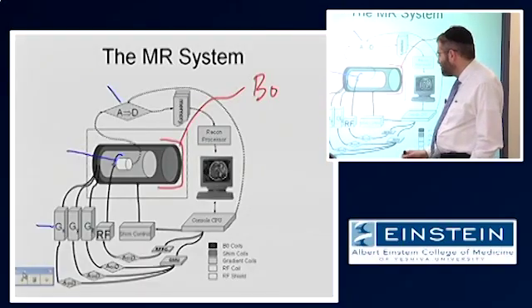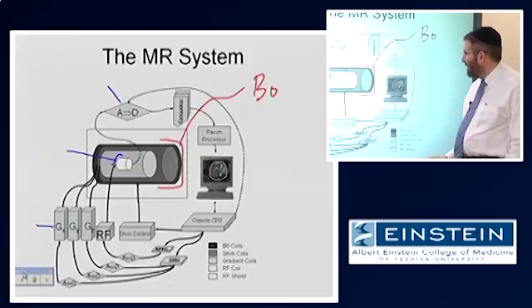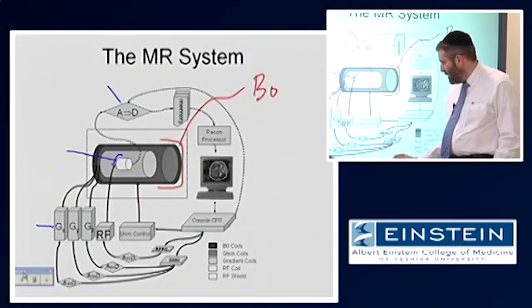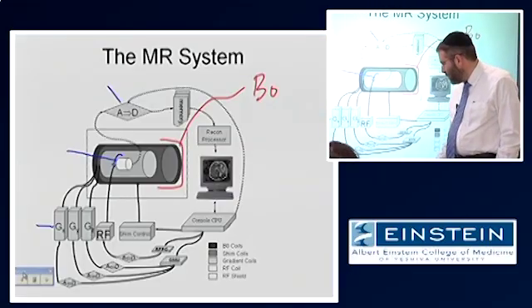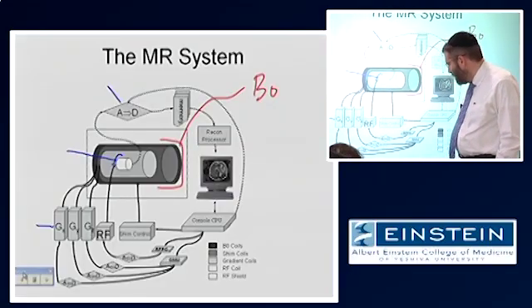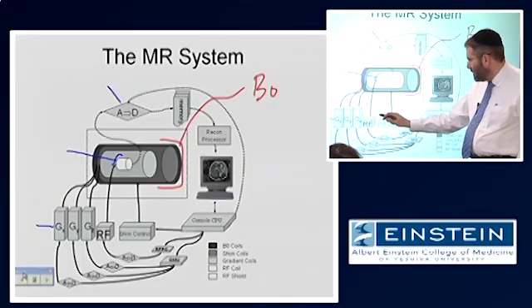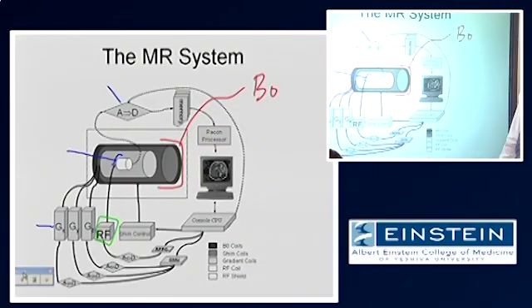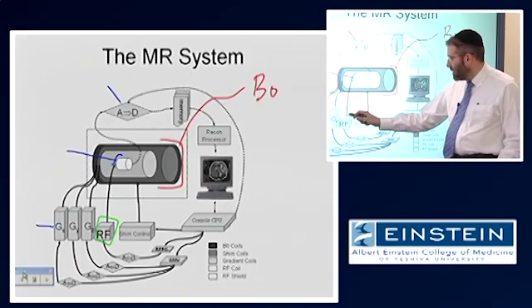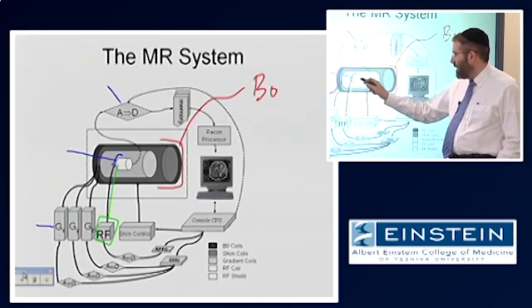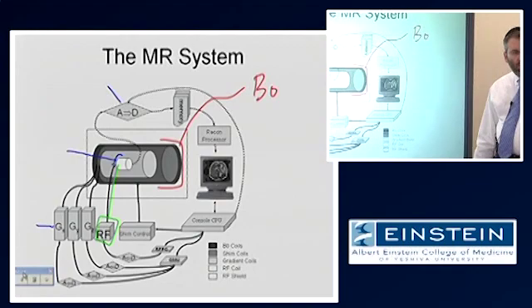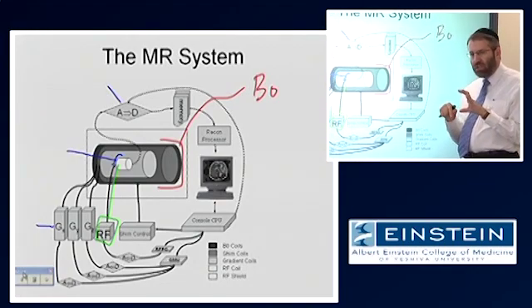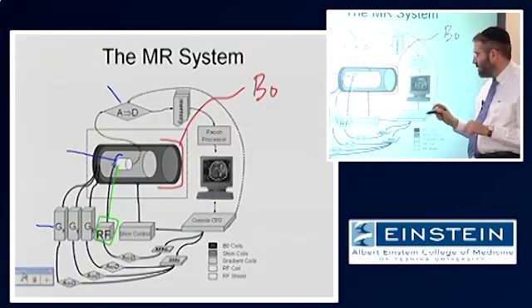and to generate the signal, we need our radio frequency system, which is basically this thing called an RF amplifier, which generates current that is put into a coil, just a loop of wire, and it's essentially an electromagnet. We'll talk about that in a little bit more detail.